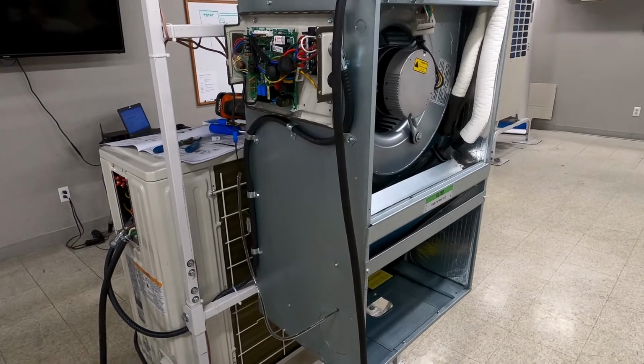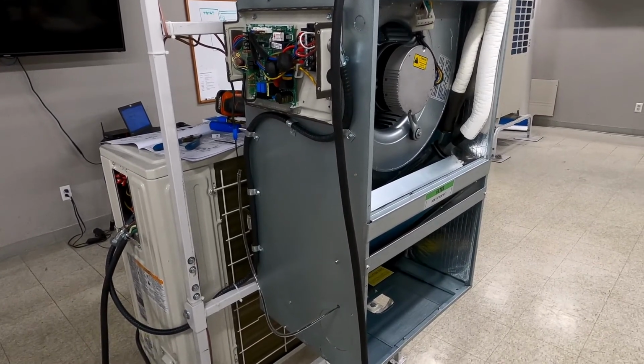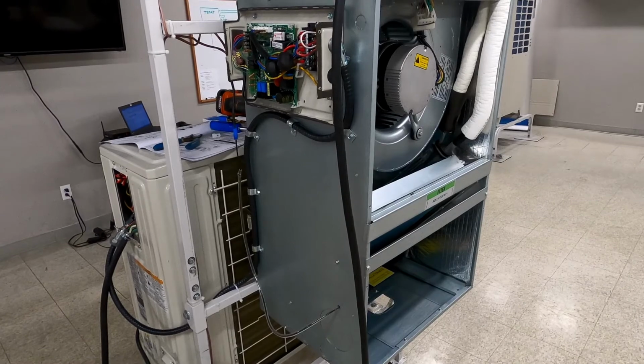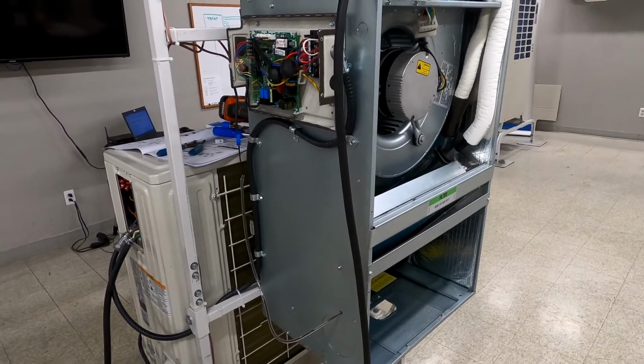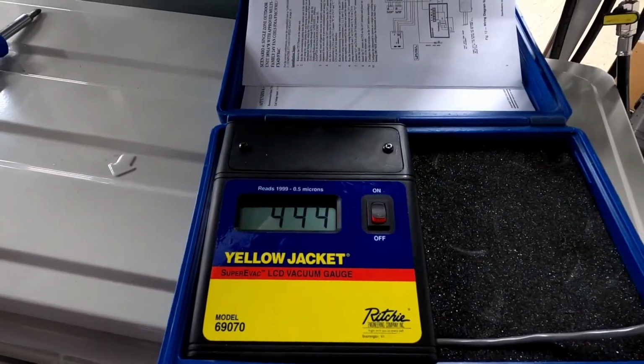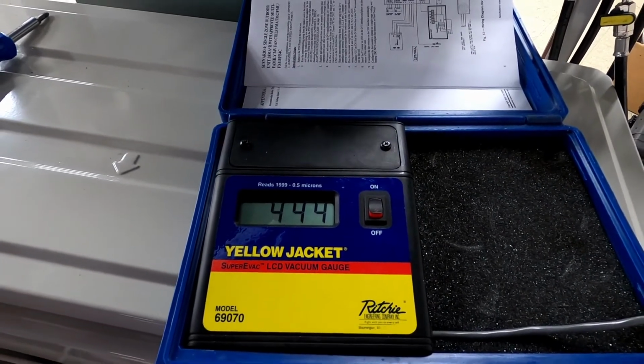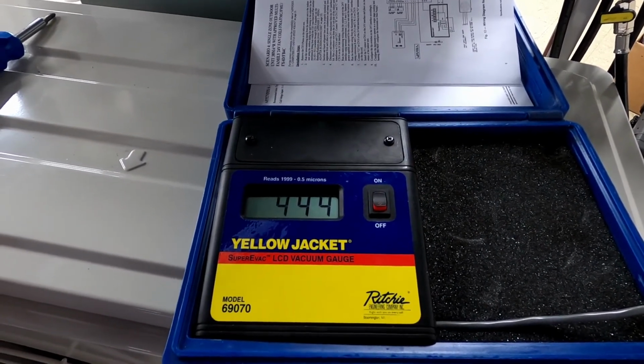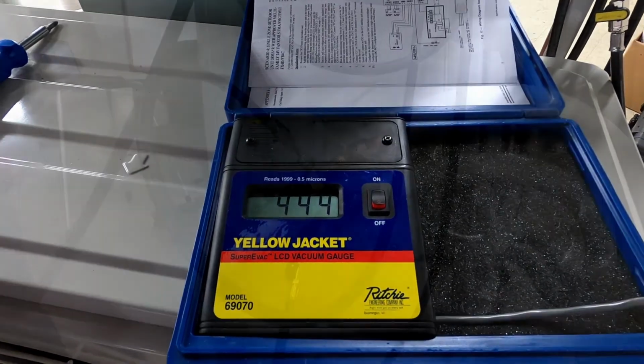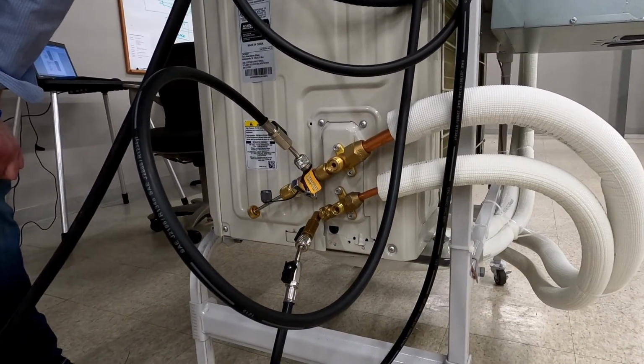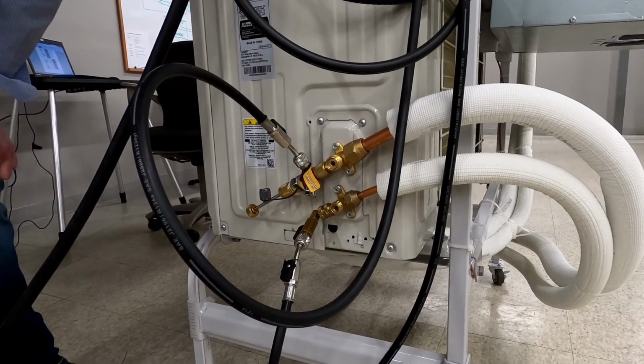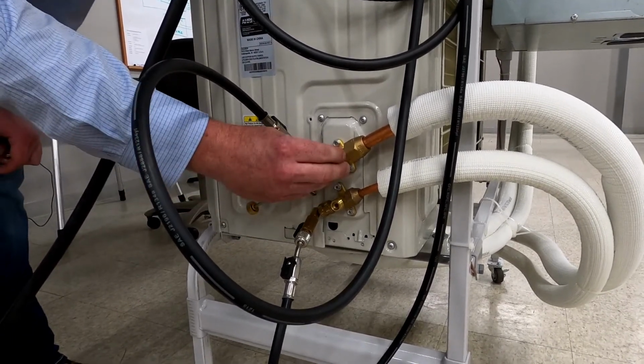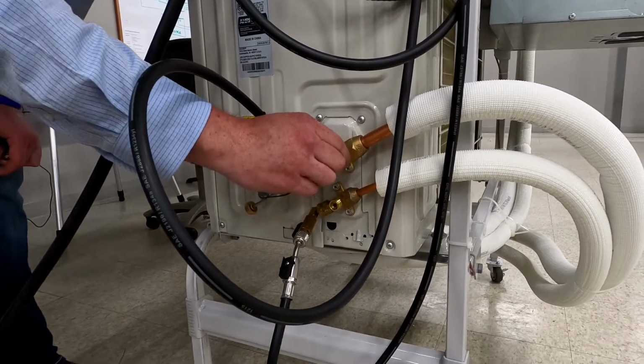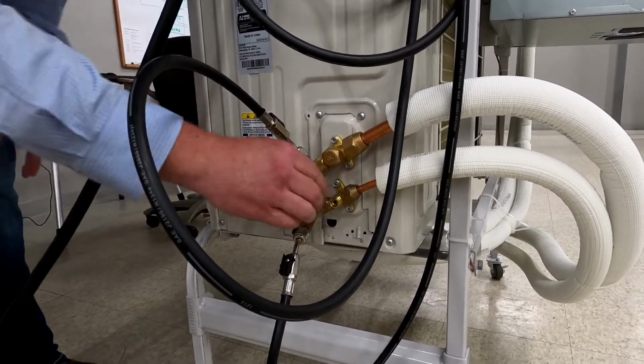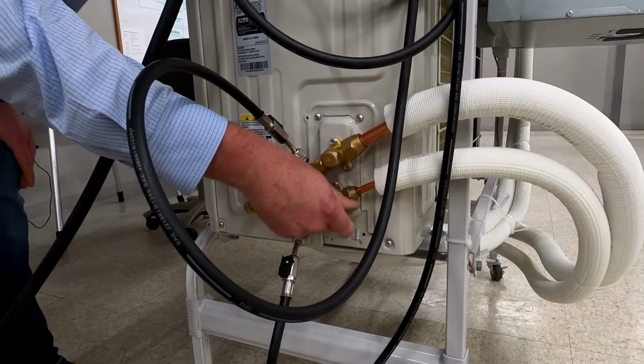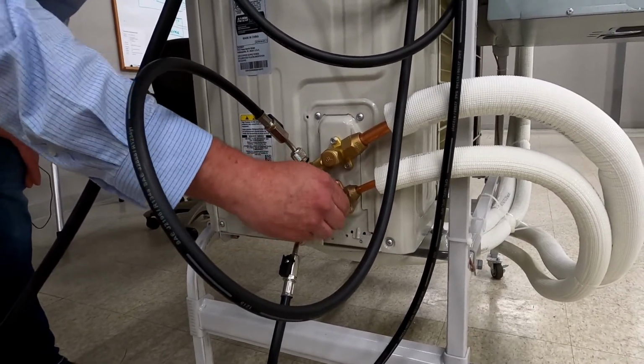By doing that, it knows what your set point is based on that return air temperature when the thermostat's no longer calling for heating or cooling. We've evacuated our system and we've held it below 500 microns for a half an hour. Now we're ready to start it up. Now that we have our service valves fully open and backseated, it's important to note that when you're putting the caps on them, that you tighten them down securely, as none of these service valves are meant to be leak-free.